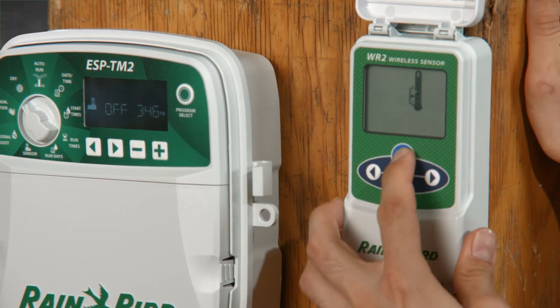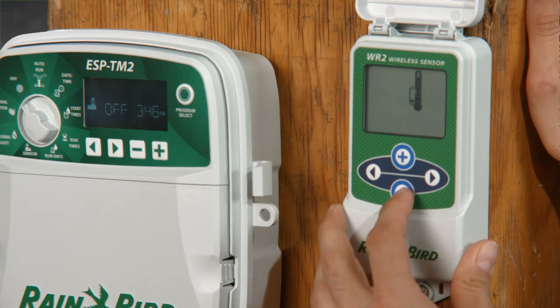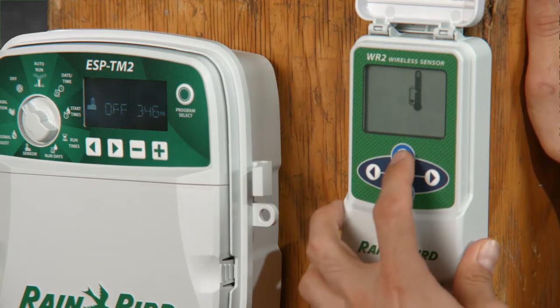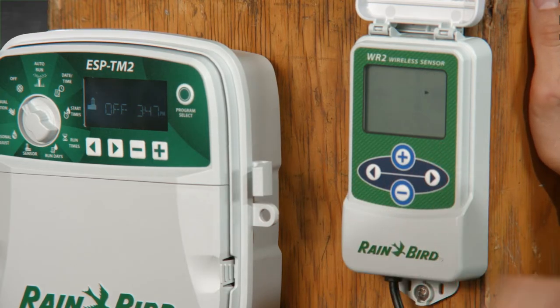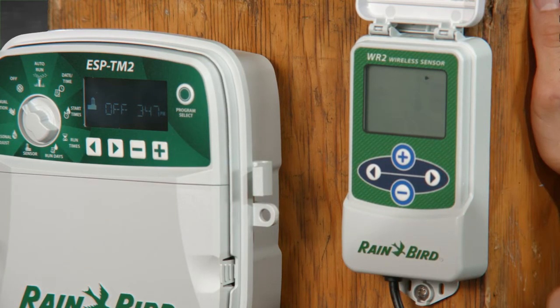There are three settings to choose from: 33 degrees Fahrenheit at the bottom, 37 degrees right in the center, and 41 degrees at the top. To adjust the amount of rainfall you receive before the interface stops irrigation, press the right or left arrow button until you see the symbol, then press the plus or minus buttons. There are six different settings here, from one-eighth of an inch at the bottom all the way to one-half inch at the very top.